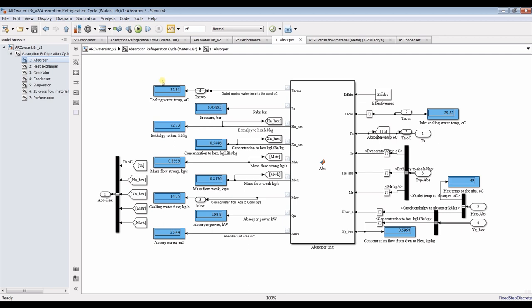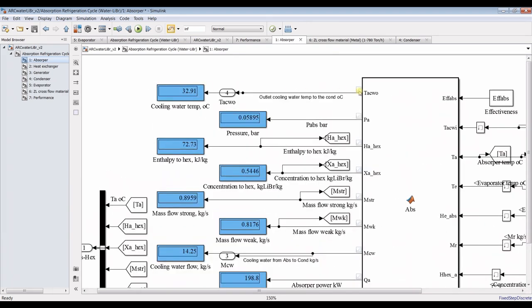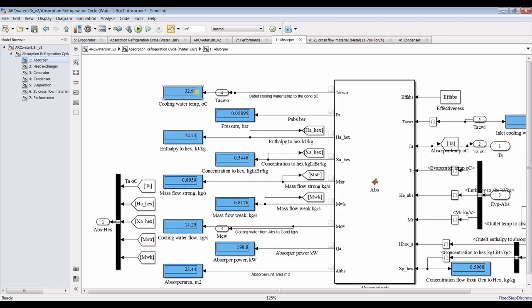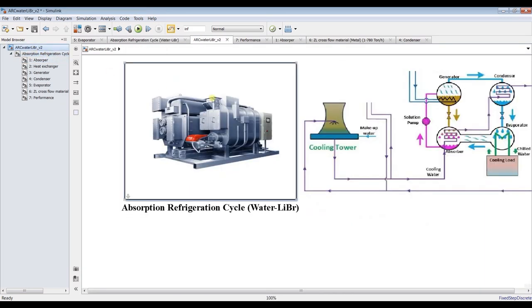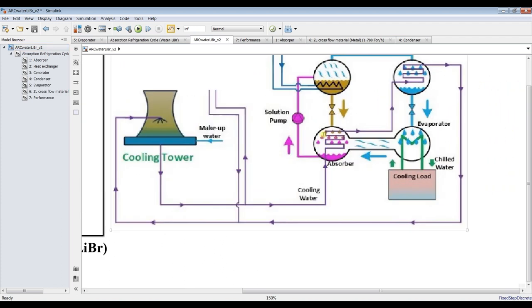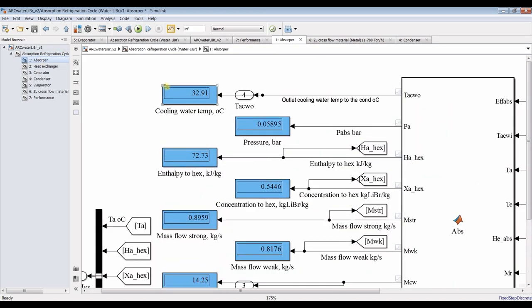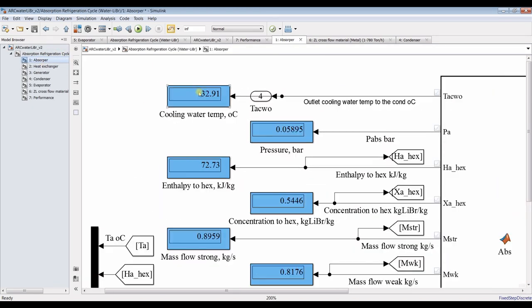Let's start from the absorber. This is the outlet cooling water — the outlet cooling water from the absorber unit going to the condenser. I'm talking about this stream: the cooling water out going to the condenser. It's around 32 degrees.